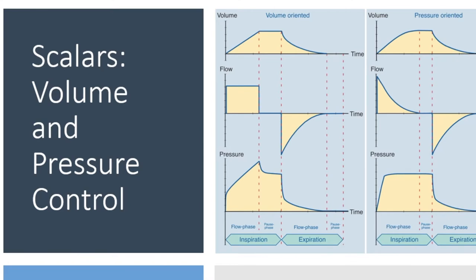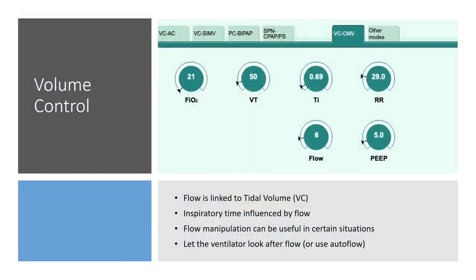Scalars are very important because if you examine them over time, they can tell you all sorts of things about the patient. You can tell if the patient wants more flow and isn't synchronizing with the vent, if there are secretions, if the inspiratory time is too long or too short, and if the expiratory time is too long or too short. I will go through these as we come across clinical situations in videos to come.